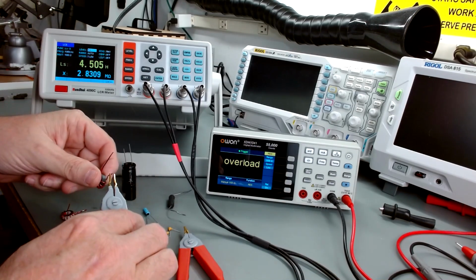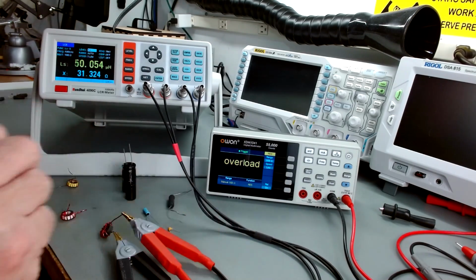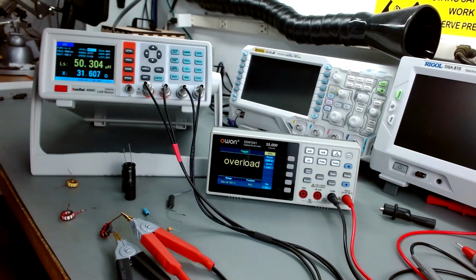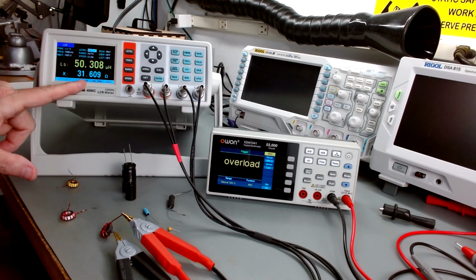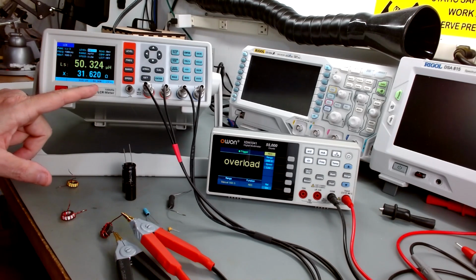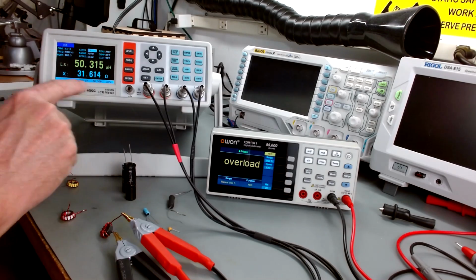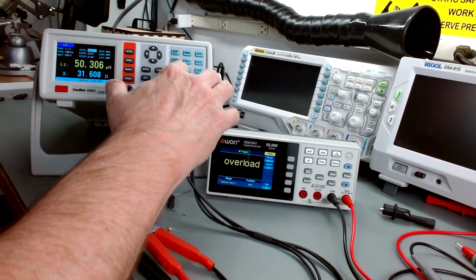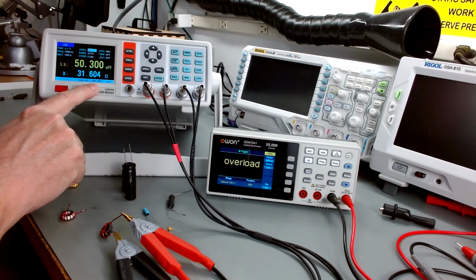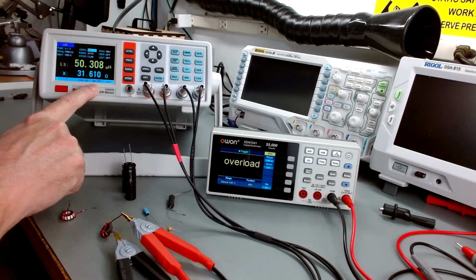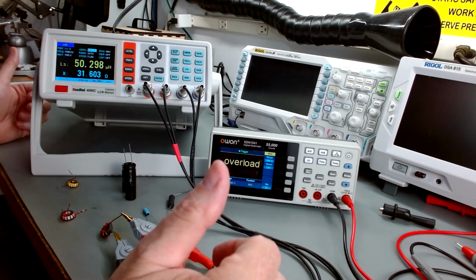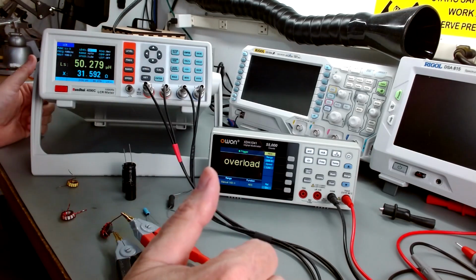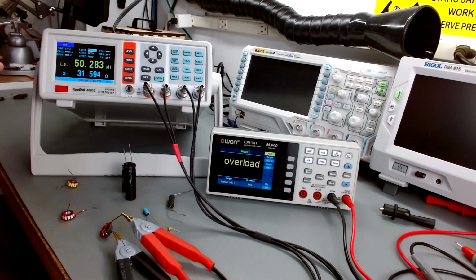There are statistical functions. For example, if I hook our inductor back up since we're set up on that right now, and go in and hit average, down here, if you can read it, it reads average microhenry 50.307, and it's averaging the readings. But if I wanted the max, I can hit max, and now it's doing the same thing with the max. It's giving me the max it has seen. I can use minimum, it'll give me the minimum it's seen. So some statistical stuff on whatever you're reading. That works on resistance, inductors, capacitors, doesn't matter.